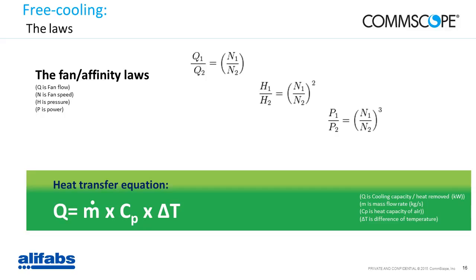Finally, the relation between the speed and the power use is a cubic relation. So that means that if we double the fan speed, we will multiply by 8 the power used, and this is very important. So often when we look at the specification of the fan or of the free cooling system, we look at how much cooling capacity it can effectively deliver at max speed. But what's very important is when those fans are running at partial load, when they're running at 50%, 60%.